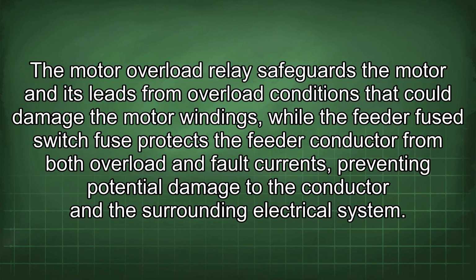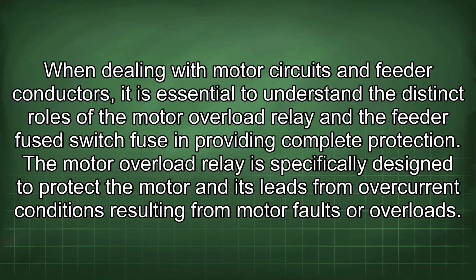The motor overload relay safeguards the motor and its leads from overload conditions that could damage the motor windings, while the feeder fused switch fuse protects the feeder conductor from both overload and fault currents, preventing potential damage to the conductor and the surrounding electrical system. When dealing with motor circuits and feeder conductors, it is essential to understand the distinct roles of the motor overload relay and the feeder fused switch fuse in providing complete protection.